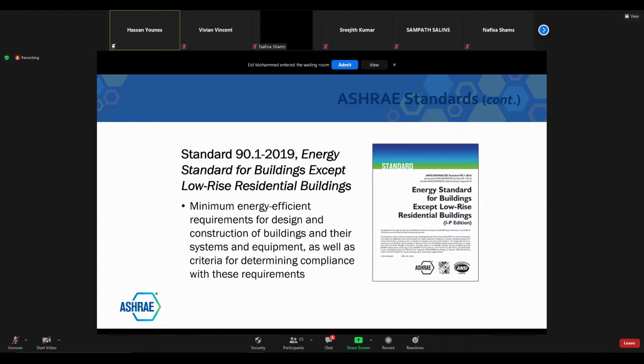90.1 tries to put a target, tries to minimize consumption by providing recommendations and requirements on how to design, what the limits and thresholds are in terms of values. For lighting in an office building, it shouldn't be more than, say, 10 watts per square meter. So for a 100 square meter room, 10 watts times 100 equals 1,000 watts, meaning only 1 kilowatt is allowable to be used as lighting in that particular room.